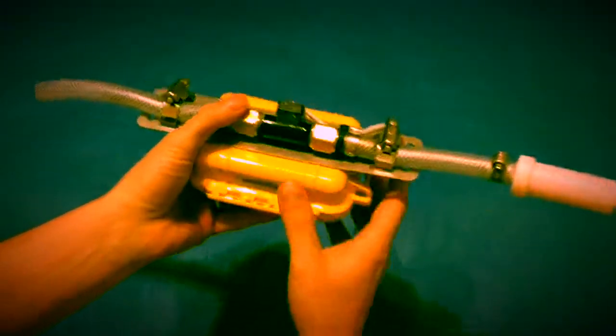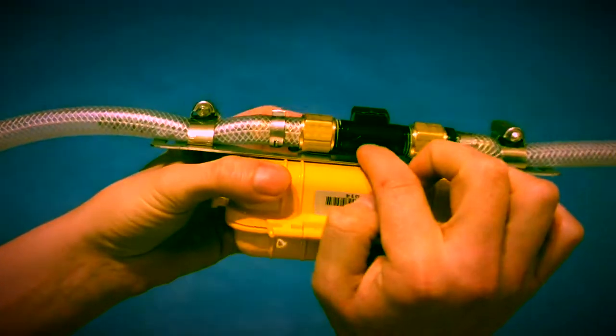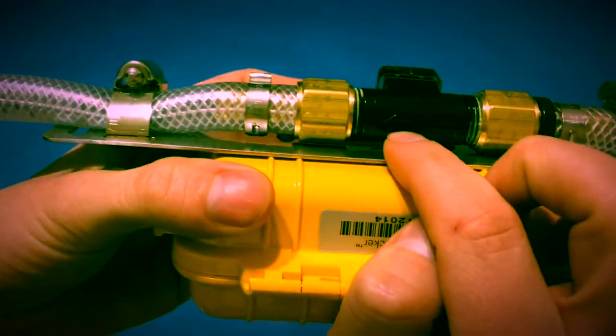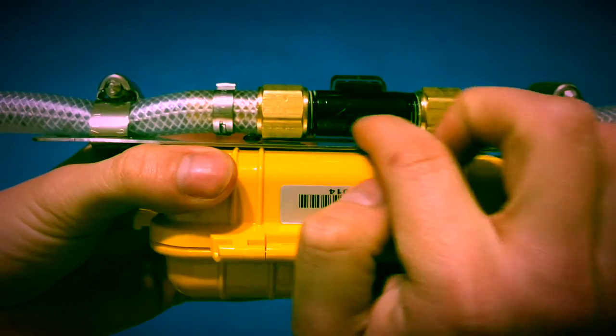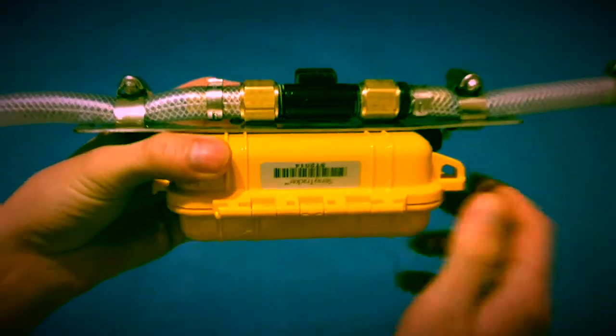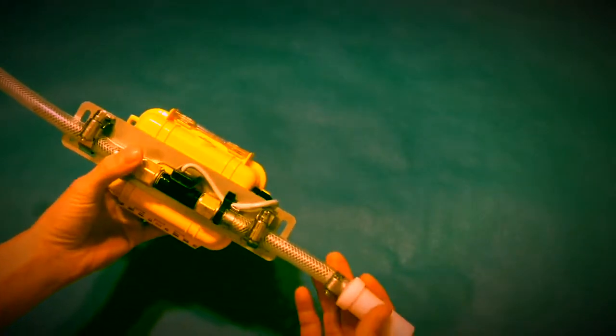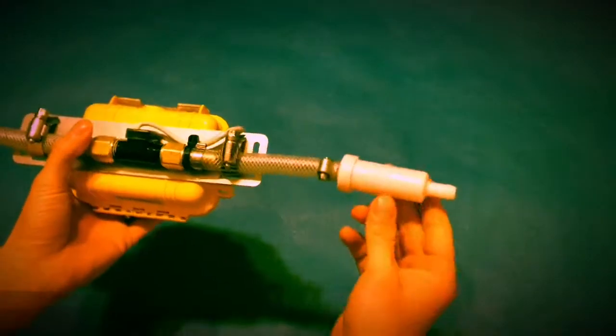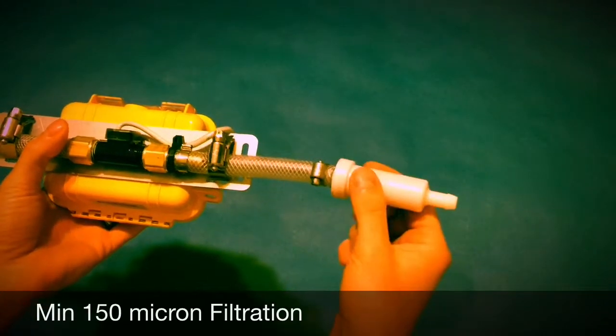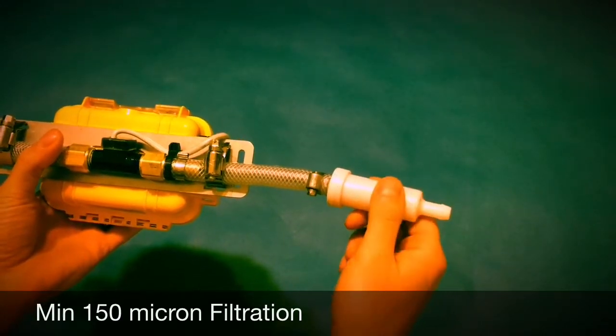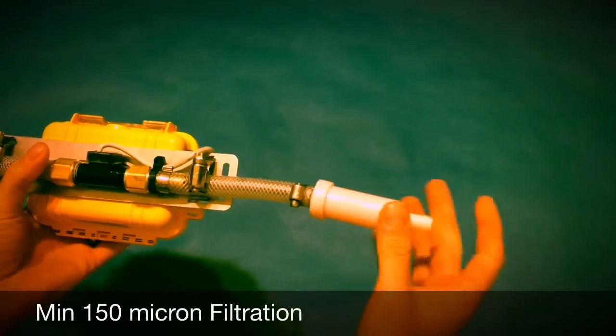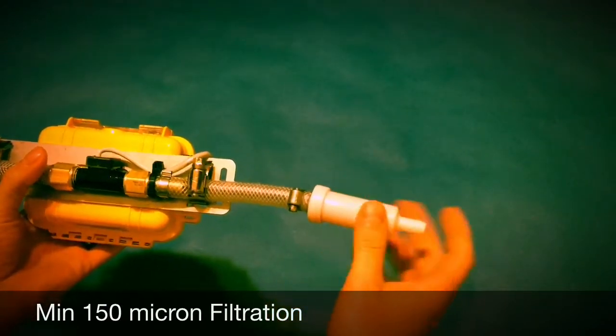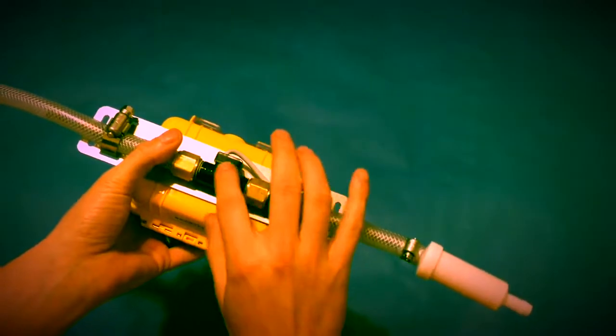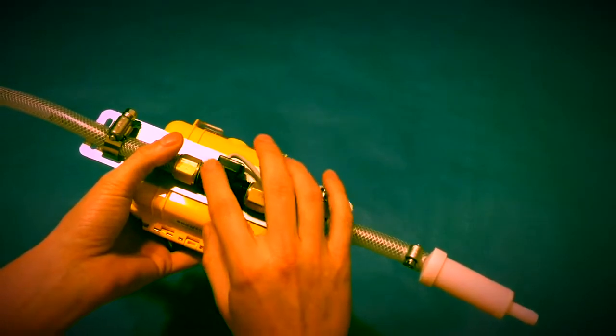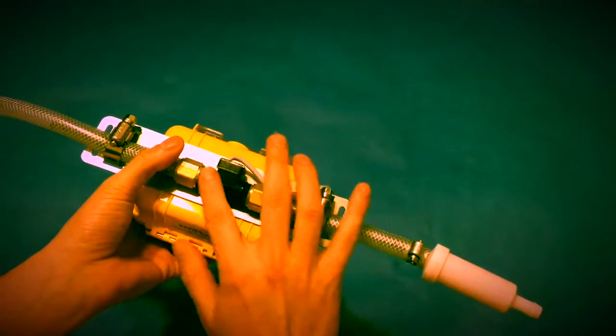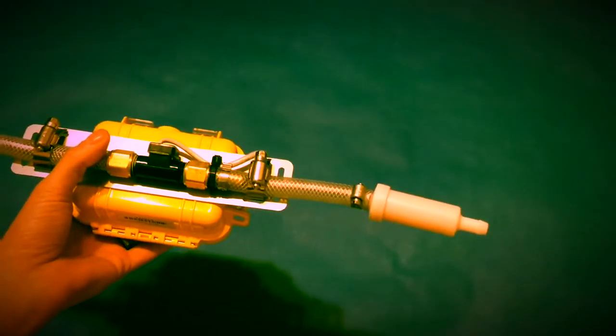You can always check that by looking on the side of this flow sensor. You can see that it's very faint, an arrow that shows the direction of flow. Other things to note, this is a 150 micron filter. It needs to be at least this or better. If you don't want to use this one, you have to at least have that much filtration beforehand. This flow sensor is very precise, and because of that is very sensitive to any type of sand and dirt inside the water.